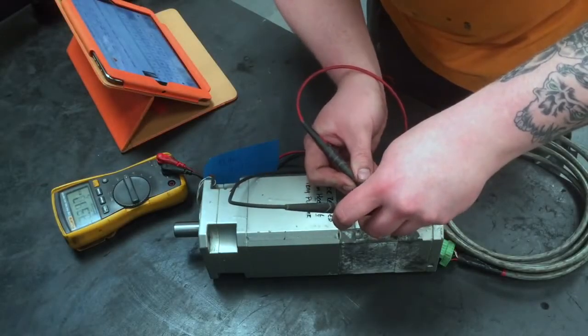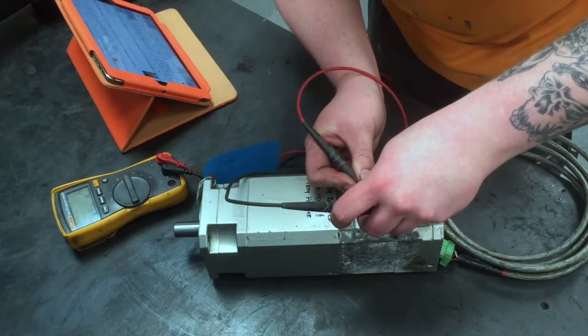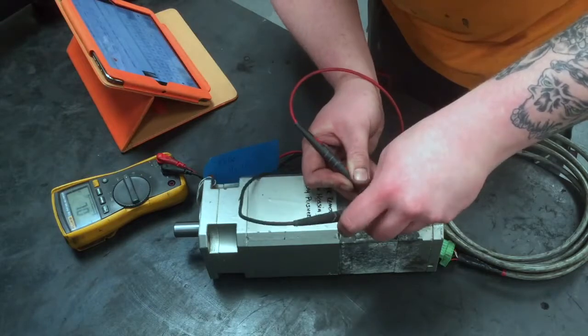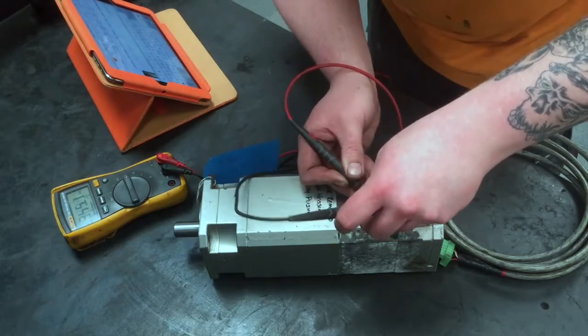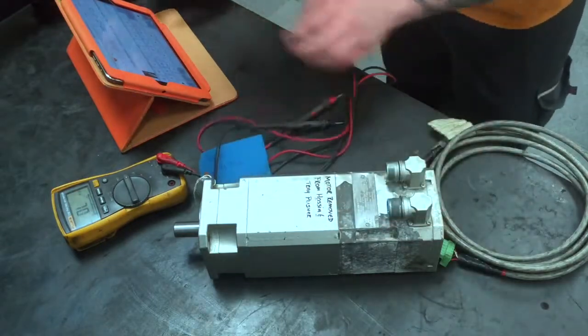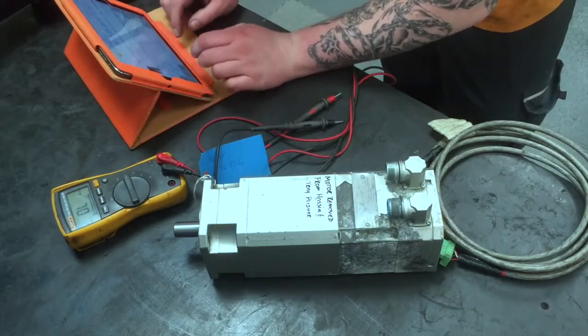Servomotors are complex pieces of equipment which are basically an electric motor with a feedback device. As we have three phase stator windings within the motor, we need to carry out basic static electrical tests first, these being insulation resistance tests and resistance comparison tests before we further the repair. All information is put into our job system for reference.